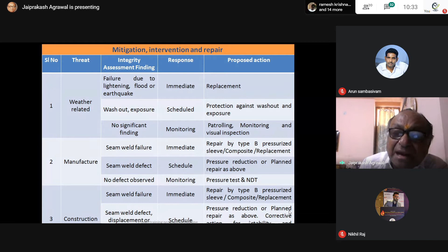External corrosion, metal loss severe such that failure pressure is less than the limit: immediate. Now reduce the operating pressure, and repair or replace within 5 days. This pressure reduction you do, but within 5 days you have to take a permanent step. How? For external corrosion, you can repair by type B pressurized sleeve, type A reinforcing sleeve or the composite sleeve. All these three are allowed.